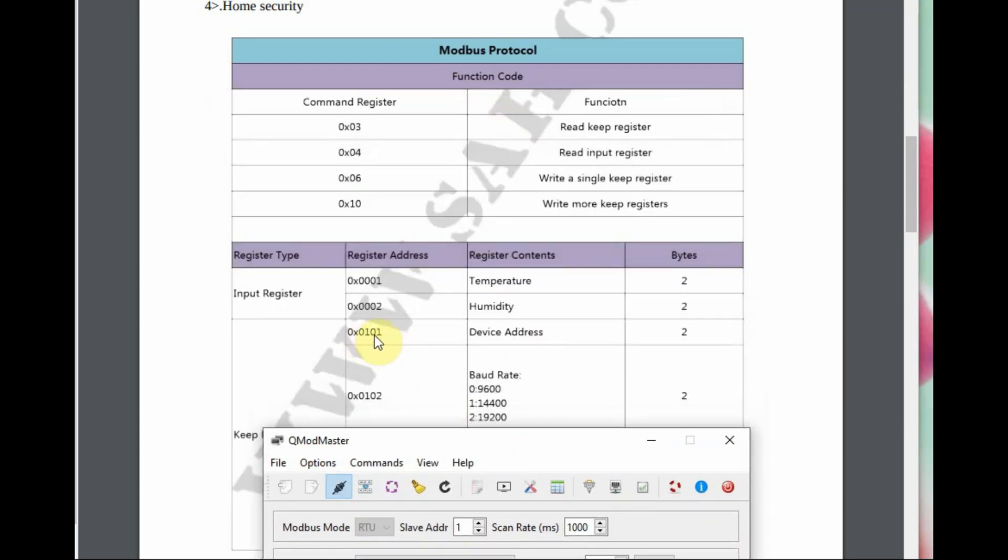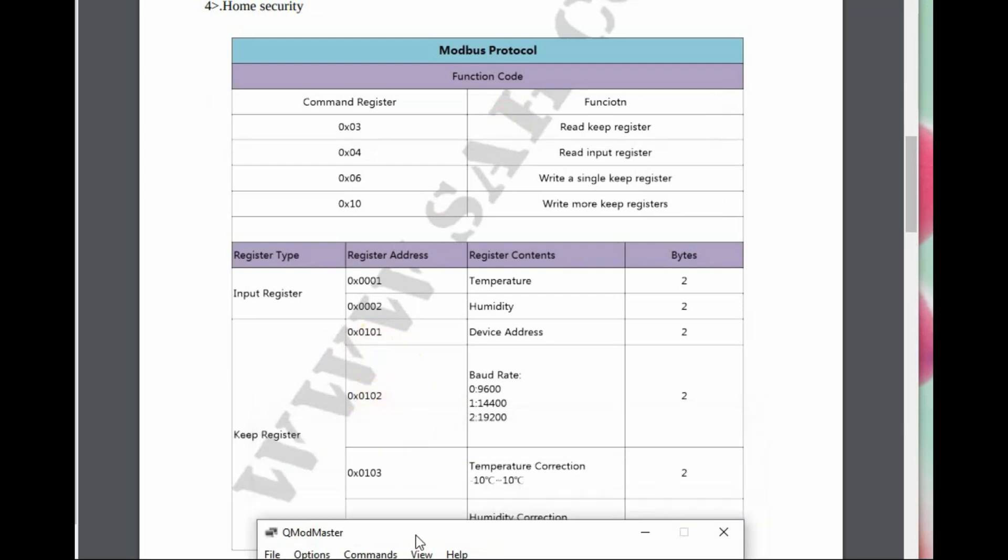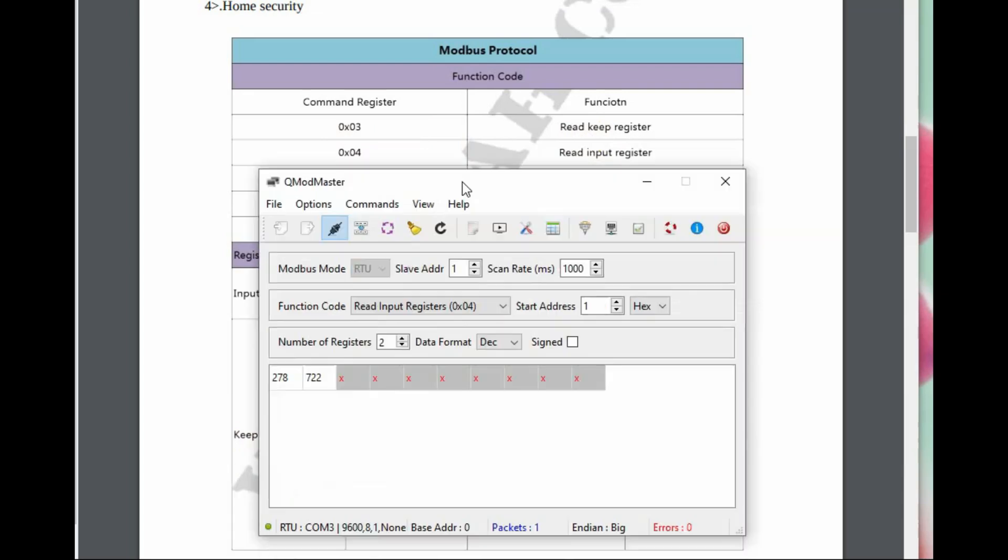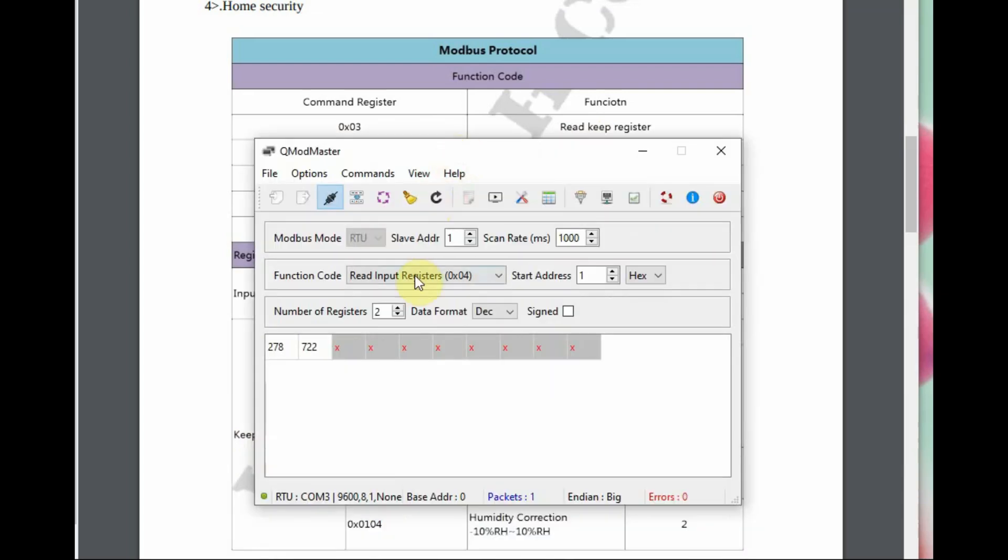Other addresses: 101, 102, 103, and 104. Address 101 is the device address location, 102 is the baud rate location, and 103 and 104 are temperature and humidity correction.